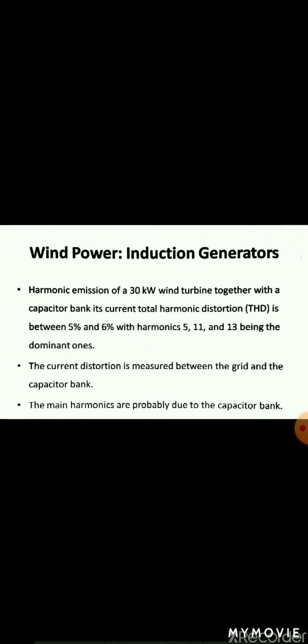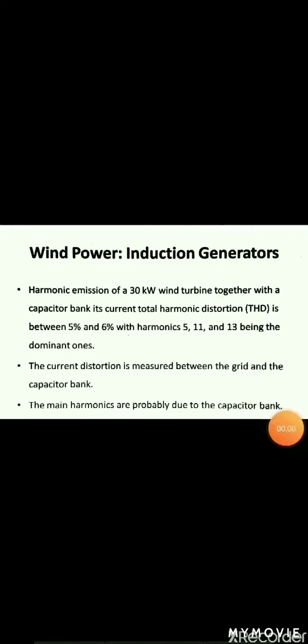Next is wind power, that is induction generator. Research has been already taken in induction generators. As per the research, the measurements show a 30 kilowatt wind turbine together with a capacitor bank. The current total harmonic distortion will be between 5% and 6%, with harmonics 5th, 11th and 13th being the dominant ones.